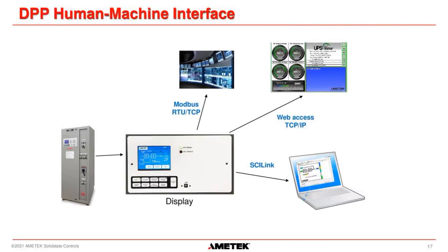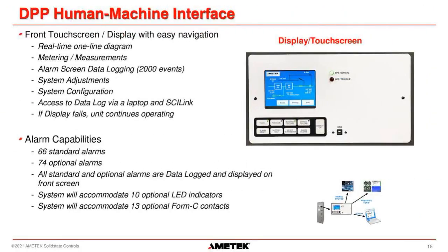I'm going to talk more about the HMI of the UPS. These are the same things we talked about earlier: Modbus RTU communication, web communication, and communication with SCI Link. So the DPP PWM UPS has the front touchscreen. This is where you can change or set your static switch position, view alarms, view data logs, view system measurements, and everything. You can also adjust set points for alarms or float voltage if you're using the conventional method. It'll view the system configuration, so how much power is available from the UPS. You can connect our Windows application SCI Link to it to download data logs or reports.